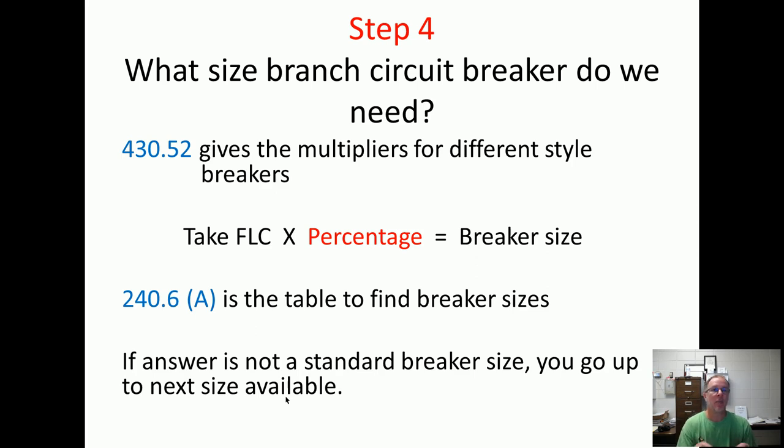That gives us our breaker size. So let's say it turns out to be 87 amps — full load current times the percentage multiplier. Well, there's not an 87 amp breaker, so we go up to 90. You can go up one size on branch circuits, but not more. So if the answer is 87 amps and the multiple choice says 70, 80, 100, and 110 — the next size up would be 90, which isn't listed, so you go down to 80. That's kind of a trick. But most of the time it will just ask you and the next size up will be there as an answer. Table 240.6A is where you find your standard breaker sizes. If the answer is not a standard size breaker, you go up to the next available size.